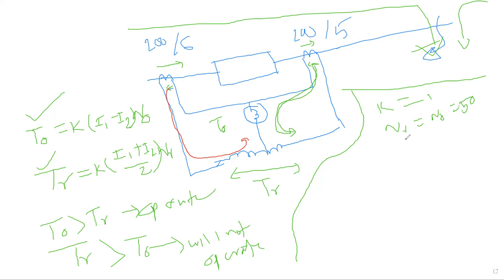All right, so let's analyze these circumstances. If it was only a differential relay, we have already discussed that, due to the inequality of the two instrument transformers, or between the two CTs, the relay would have operated under this external fault if the CTs are not the same. So is that limitation resolved or not here with the improved version? Let us check first.